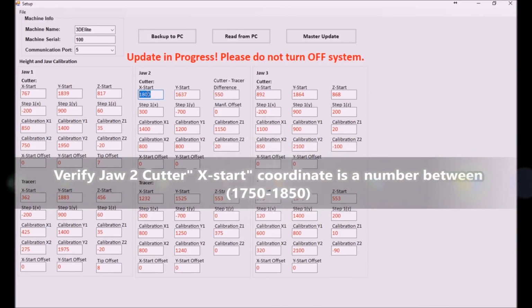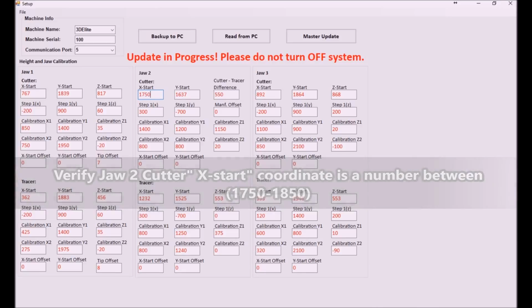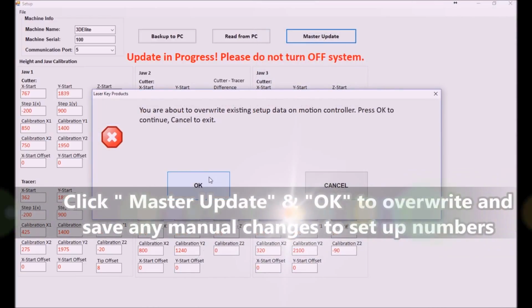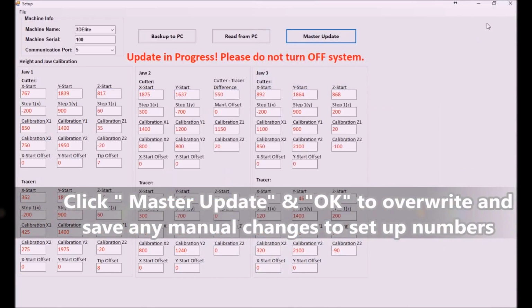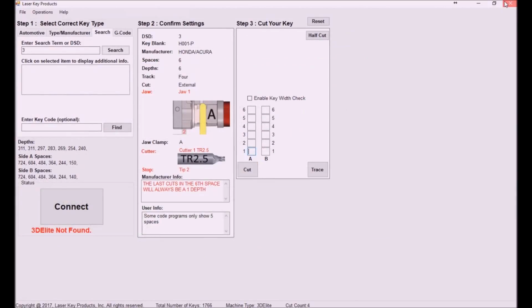The X-start coordinate under Jaw2 cutter setup data needs to be in the range between 1750 and 1850. If that number is not there, manually insert a number in that range, then click Master Update and OK to save to the board.